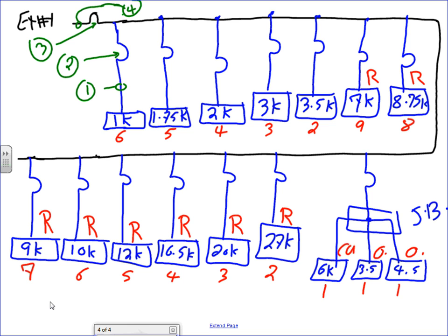The voltage system, just to be consistent for this, let's use a 240 volt, so we know, 240/120 volt, single phase. Single phase. And all this equipment, because I need to size branch circuits, I'm going to assume all this equipment is 240. We're rating all of them at what voltage? 240. If it was 120, what would you do? You just divide by 120. We're going to rate all this equipment at 240. Let's go size them.